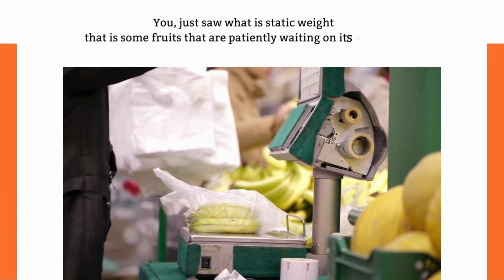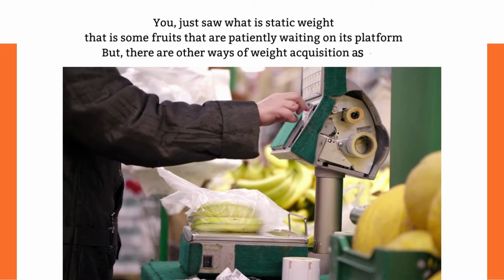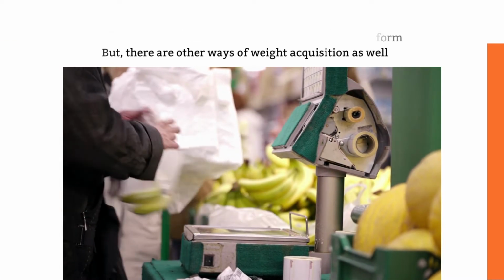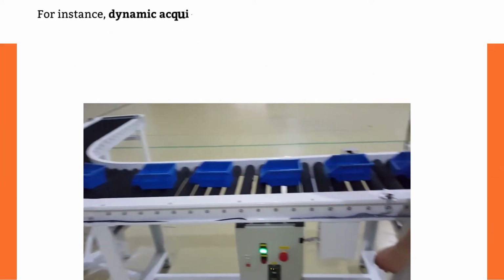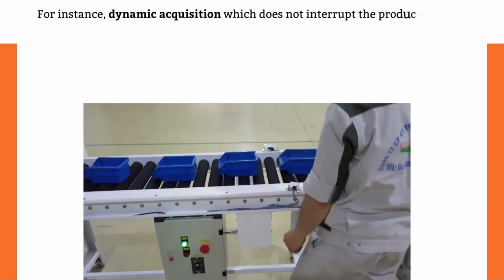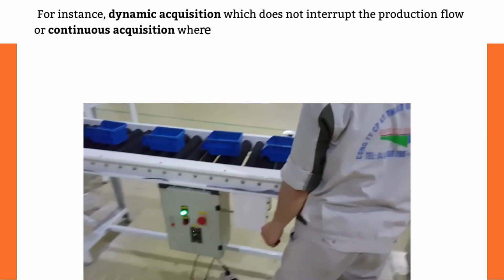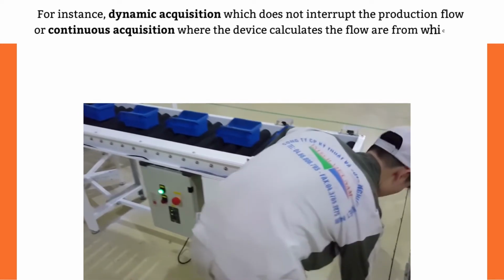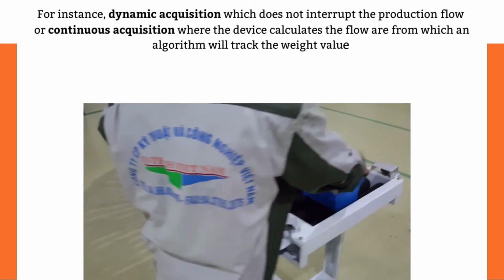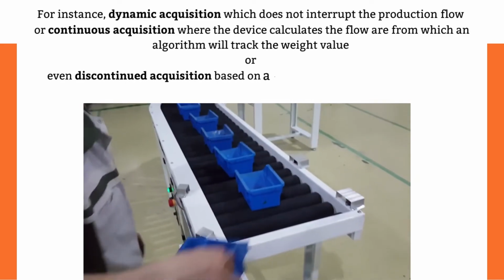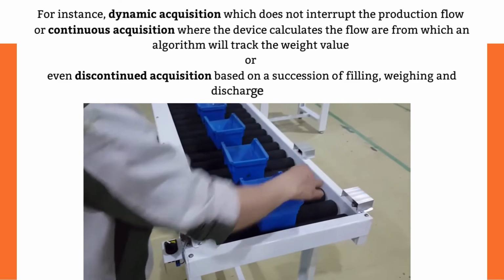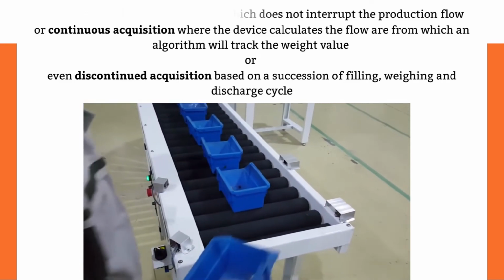That is some fruits patiently waiting on its platform, but there are other ways of weight acquisition as well. For instance, dynamic acquisition, which does not interrupt the production flow, or continuous acquisition, where the device calculates the flow or from which an algorithm will track the weight value, or even discontinuous acquisition based on a succession of filling, weighing and discharge cycles.